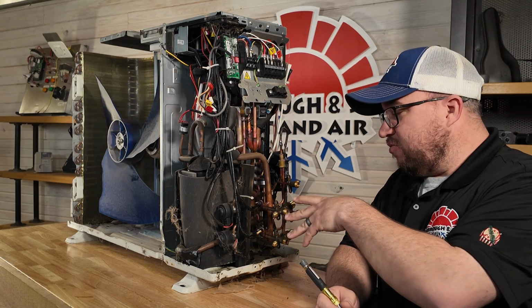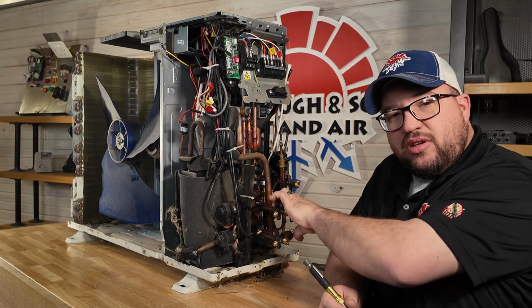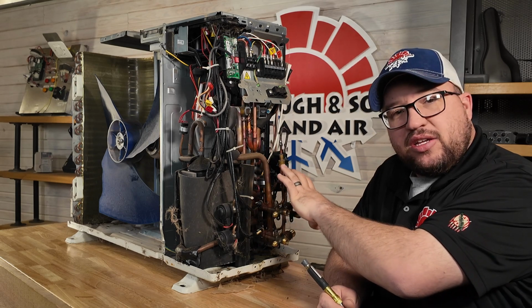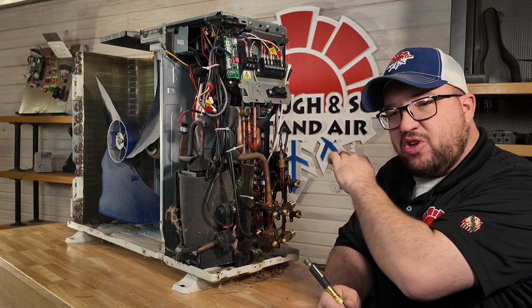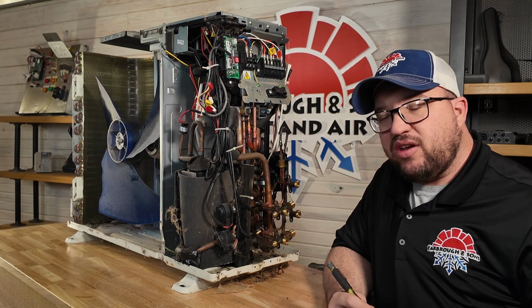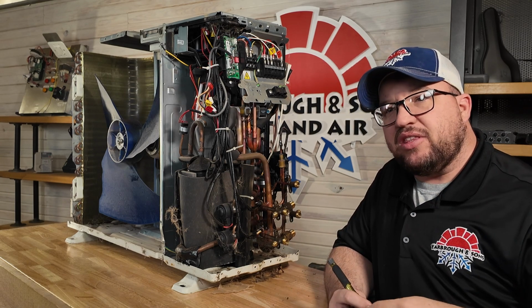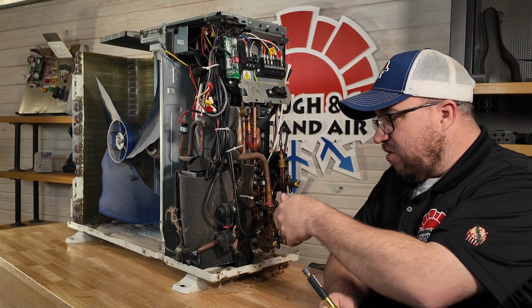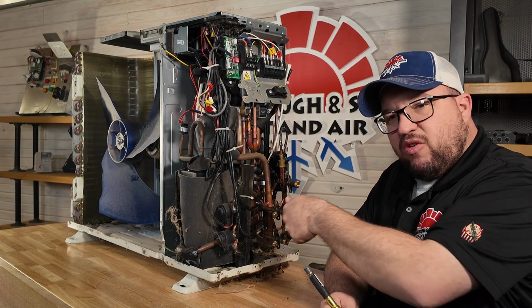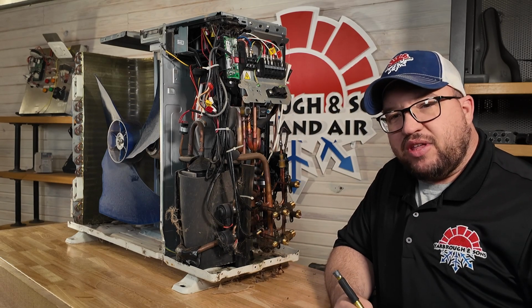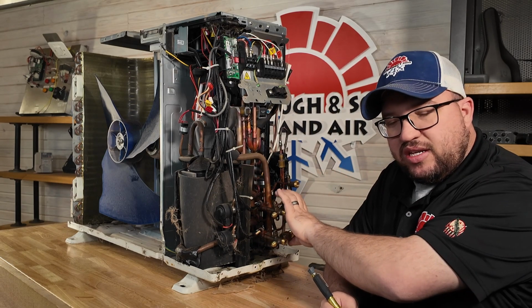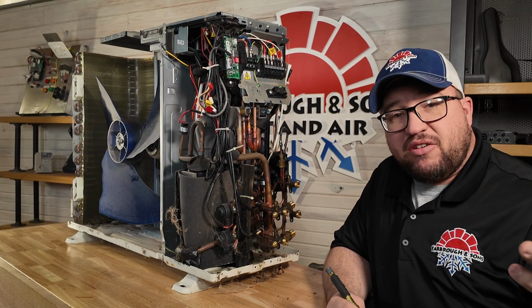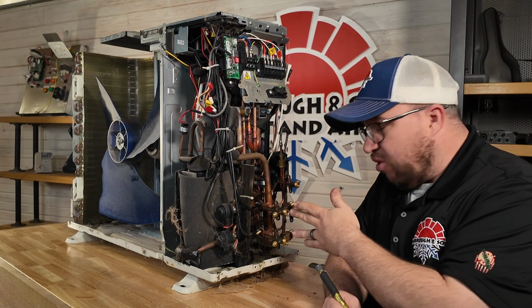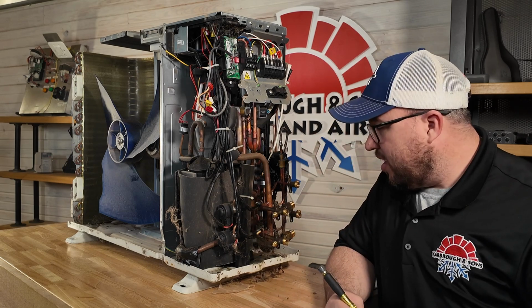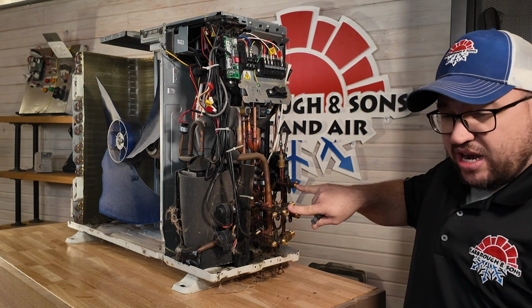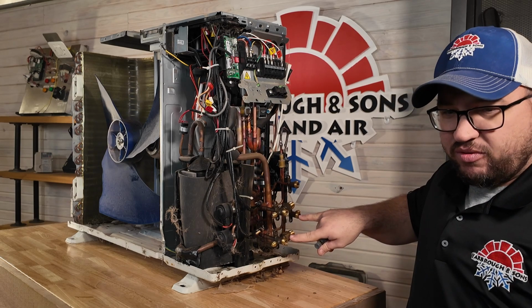With these service valves, what they're actually going to do is tie onto your actual copper line. So we do that with flare fittings. A majority of these are flare fittings that tie on, which is great because you run into fewer problems than if you're tying in and welding. A lot of people don't weld with nitrogen, so that causes other kinds of problems. So flares are great on these, and I'm a big fan of flares. We've been using them for years, and as long as you do it per the manufacturer specs, you won't have any problems. As you can see, we got two sets. You got your unit A and your unit B, some of them call it different, just 1 and 2.